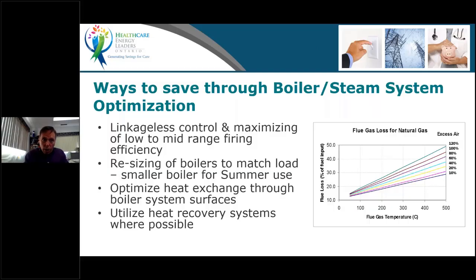What's not written here, and I want to emphasize that, if you ask your boiler operator or your plant operator, what is the efficiency of my boiler plant? He's going to very likely tell you, oh, it's really high, it's 85% or it's 86%. He's going to read off the combustion test results. That is combustion efficiency. You have to be very careful. This can be very far from the actual annual efficiency of a boiler. So if you've got an atmospheric boiler, for example, you could easily get 82, 83, 85% combustion efficiency, but your yearly efficiency can be as low as 60 or 65% because of the stack losses in an atmospheric boiler. So always be careful when they talk about efficiency. You want to optimize it, but you want to optimize the actual annual efficiency, not just the combustion efficiency.